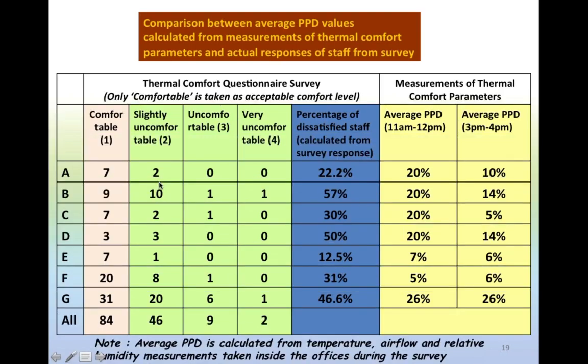From the thermal comfort questionnaire survey in all these seven office spaces, we did two kinds of computation. One is the usual PMV, PPD computation, as I mentioned, and here you notice that in the morning and afternoon there were, well, 20% dissatisfaction, but later on it wasn't that bad. So you notice that the conventional or the typical PMV, PPD didn't show there was any serious issue there.